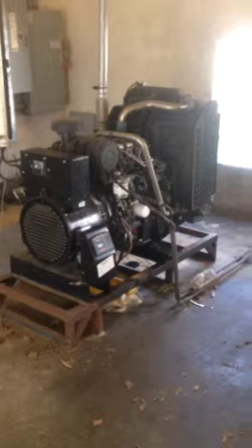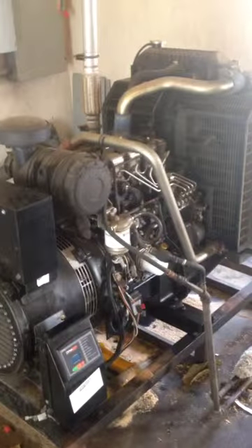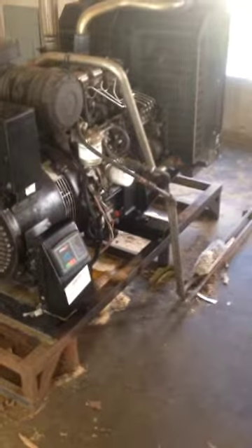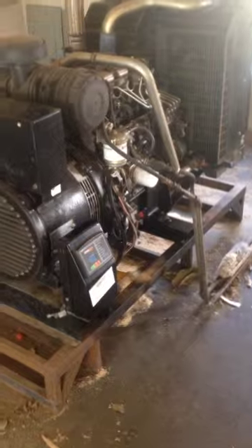So, to me, that tells me that maybe this transfer switch over here is becoming the problem. First, it was blowing the fuses on the generator. Couldn't figure out why. It was just a temporary surge of power that would blow that fuse over here. When the fuse first started blowing, it just blew the fuse like a normal fuse would. But after a while, it started melting the plastic and, I mean, destroying it. Like it was big power coming through. It was only temporary. After you replaced the fuse, if I raked the new fuse over the terminals to diffuse the phantom power, then after that it was fine.